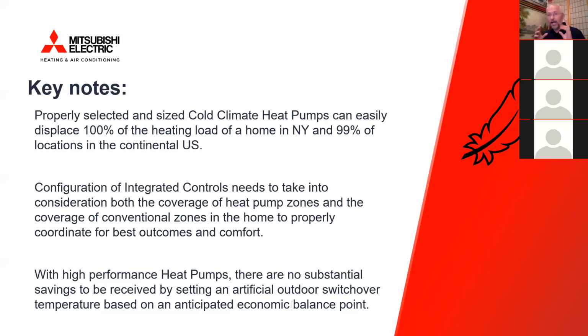Okay, so the other key thing, and I'll come back to this at the end of the slide deck: when you're doing integrated controls, one of the most important things is to make sure that you understand not only the coverage of the heat pump zones, but you also take into consideration what the coverage of the conventional zones are and how those are either aligned or different, because that's something that you're going to want to look at. If you have zones that are different, meaning you've got parts of the house that don't have coverage from ductless heat pumps, but they do have coverage from conventional heating systems, there may be points in the winter when those extraneous parts of the house, those far distant parts of the house, get much colder.